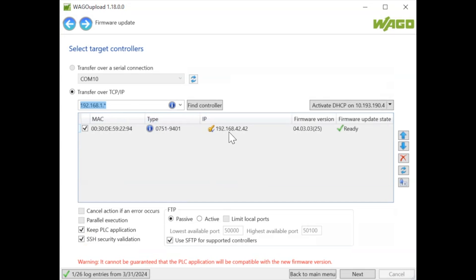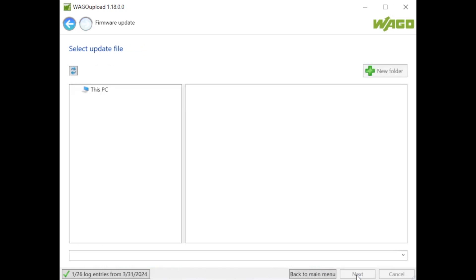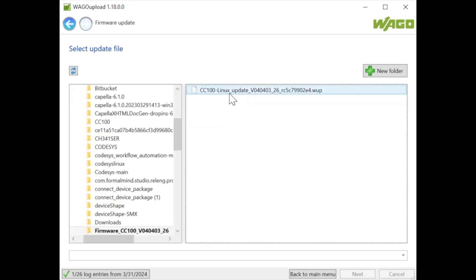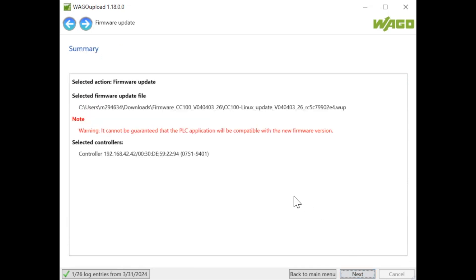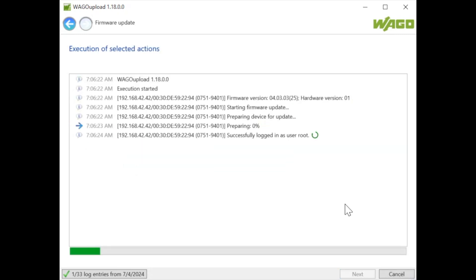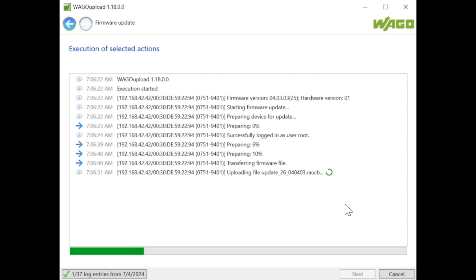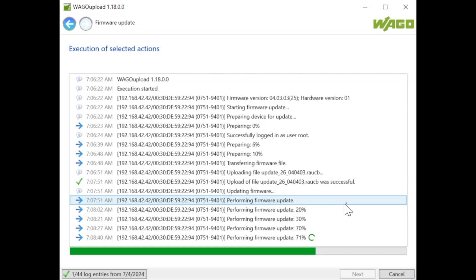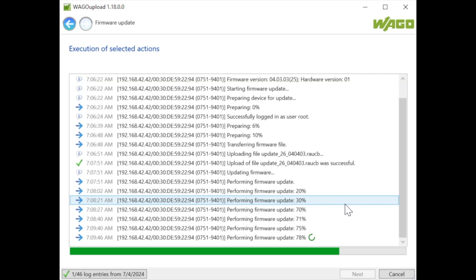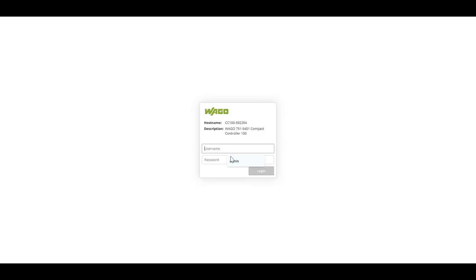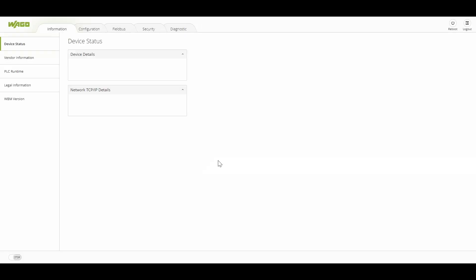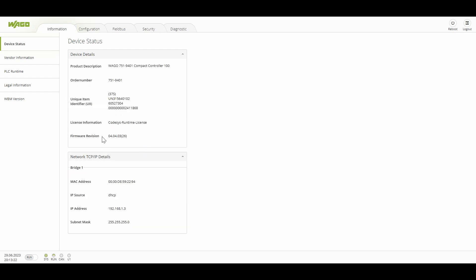We can update the firmware using the WAGO Upload Tool by finding the controller using its IP address. We are connected via USB-C cable and the default IP is 192.168.42.42. We click next, search for the firmware file we downloaded, select it, click next, and the upgrade process will start. It will give you some warnings — based on those you can make your decision. Once you click next it will proceed with the firmware upgrade, which takes some time. After the upgrade, we can verify by logging into the web server using the default credentials, where we can confirm the firmware version has been upgraded to 26.